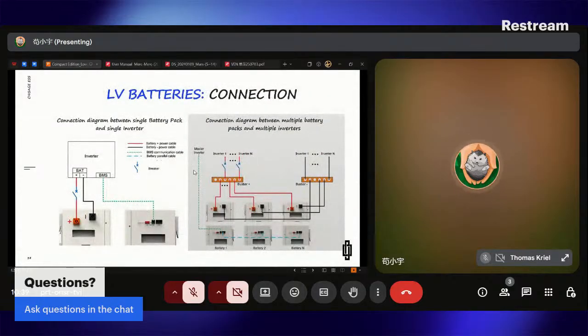So this is the wiring of the batteries. The left side is the single battery, so you only need to connect the battery terminals and the BMS, so just the 3 cables. And the second one is the parallel connection. So you connect all positives and all negatives to the bus bar, and then connect the bus bar to each inverter and parallel the communication cable. And also we have another way to parallelize them. It's a little bit different, and we already showed it in previous pages.